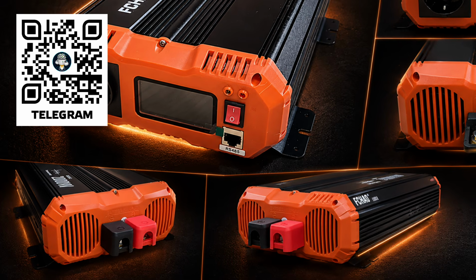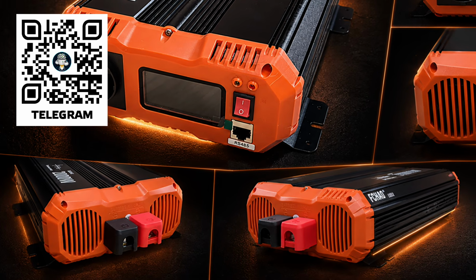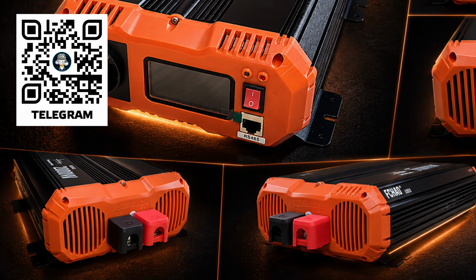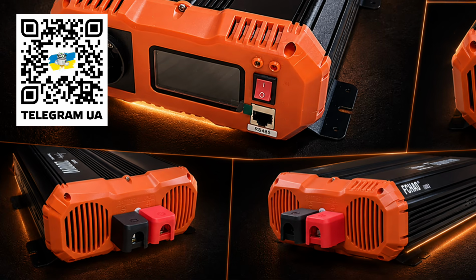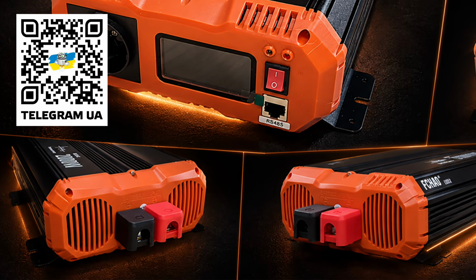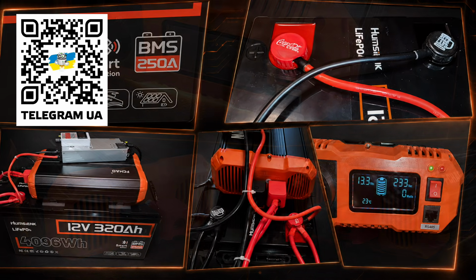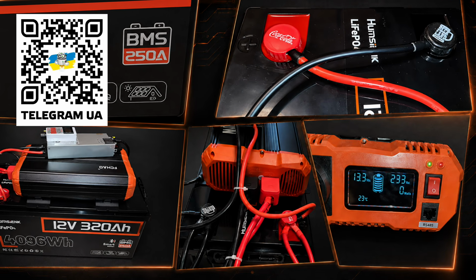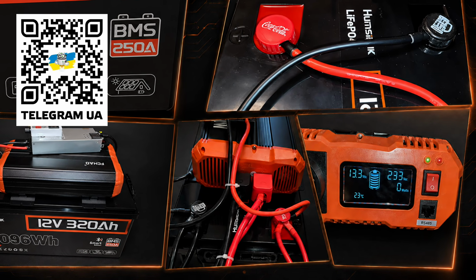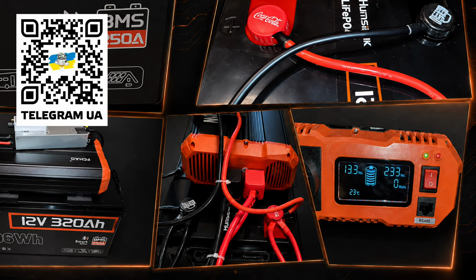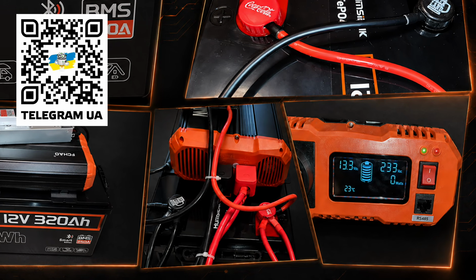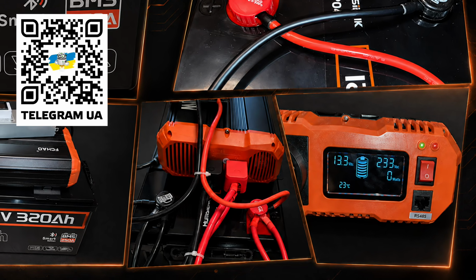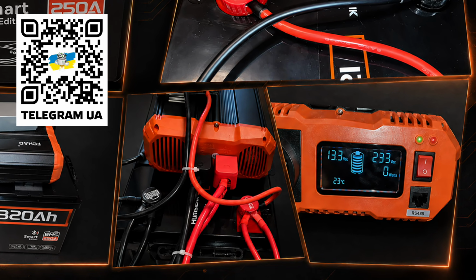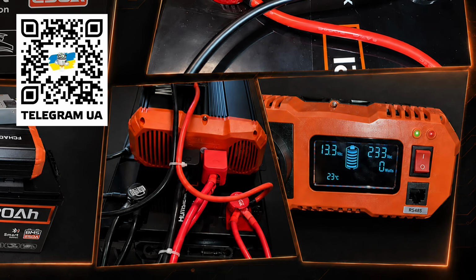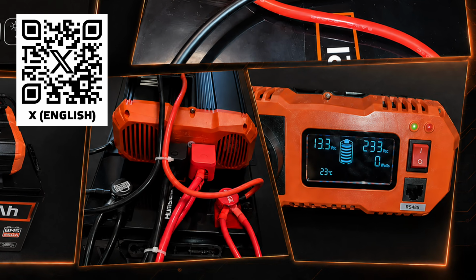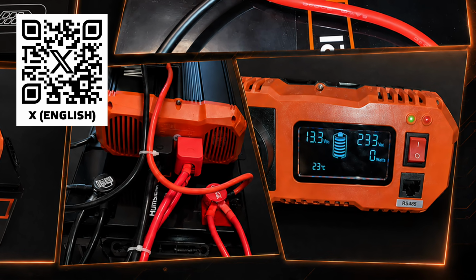The only thing I could add is that if you plan to use it at near maximum loads, around 2 kilowatts, for a long time, I would either replace the battery wires with even thicker ones or add 1 or 2 more pairs. In the kettle test, they became quite noticeably warm. But in the heater test at 1.3 kilowatts over several hours, they remained simply well warm. The battery test also showed that the real parameters matched the declared ones despite the high discharge current, which is also a good test in itself.